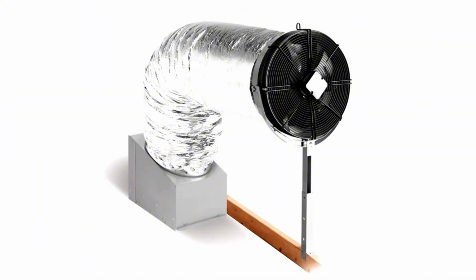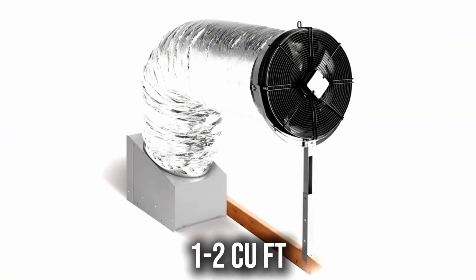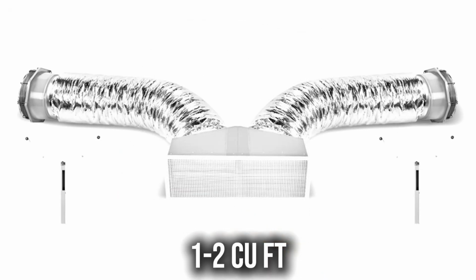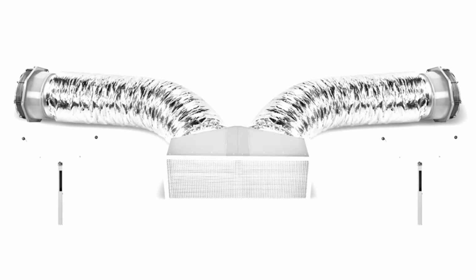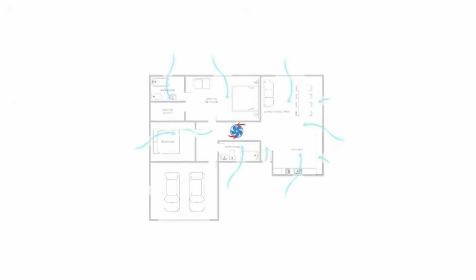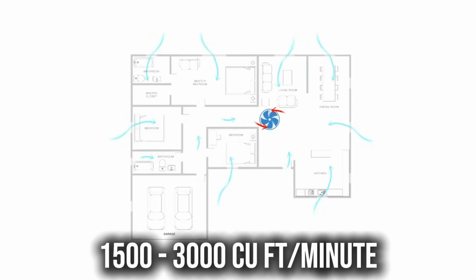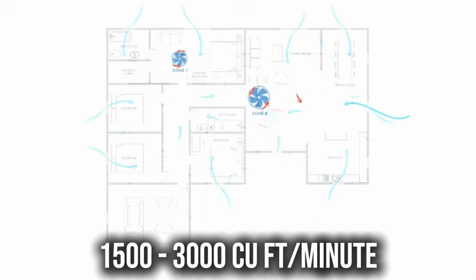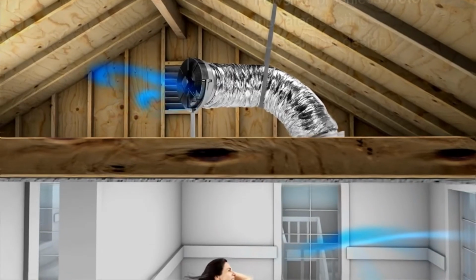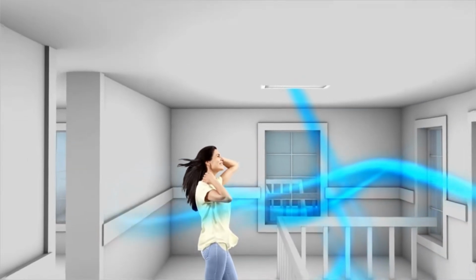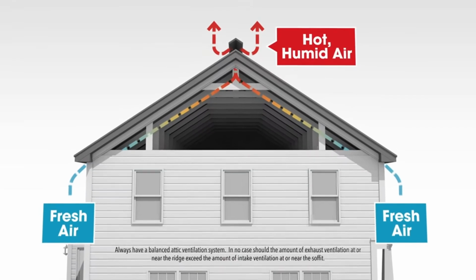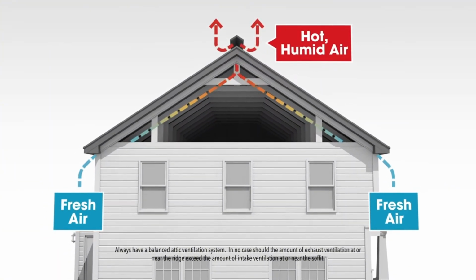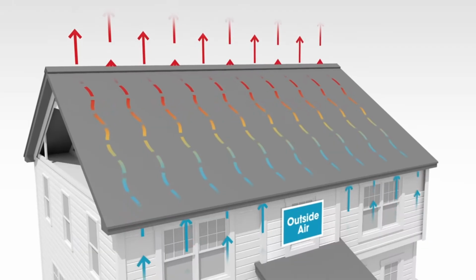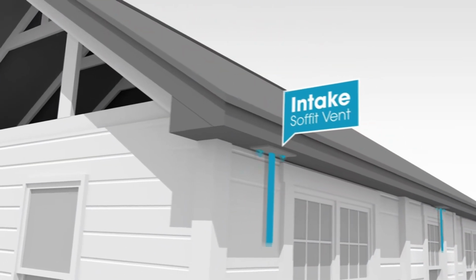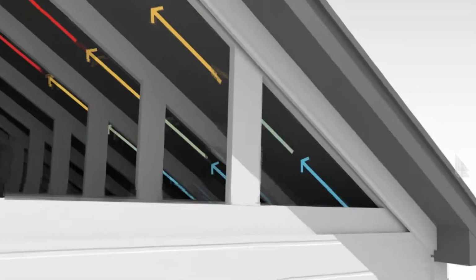For sizing, the general guidance is 1 to 2 cubic feet per minute of fan capacity for every square foot of floor space. A 1,500 square foot home typically needs a unit rated between 1,500 and 3,000 cubic feet per minute. The key measurement to verify before installation is your net free vent area, the actual open area through your gable vents accounting for the screen mesh. Most older homes with functional gable vents already meet the requirement for units in this size range. An HVAC contractor familiar with whole house fans can do this assessment in under an hour.